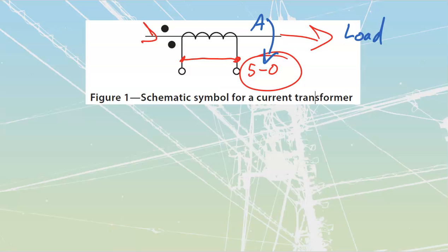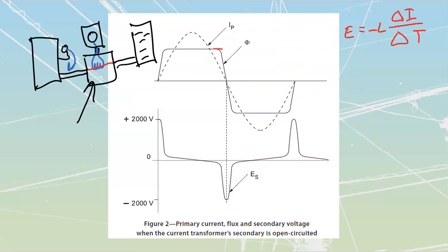Right underneath this picture there's a big exclamation mark that says make sure, before you remove it, that you short circuit or bridge those secondary terminals so it doesn't cause any problem. Underneath that, they say some CTs are designed with a special shorting bar that's supposed to short the secondary circuit, the 5 amp circuit, anytime the cover on the transformer terminals is removed. Do not depend on it — make sure you verify it.